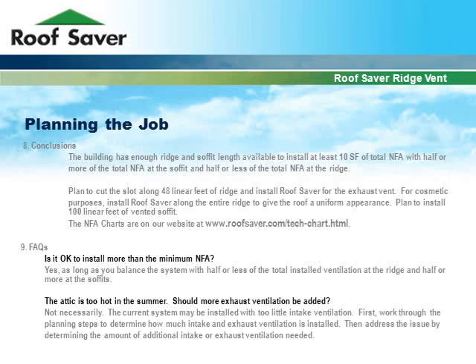You may ask: is it okay to install more than the minimum net free area? Yes, as long as you balance the system with half or less of the total installed ventilation at the ridge and half or more at the soffits.